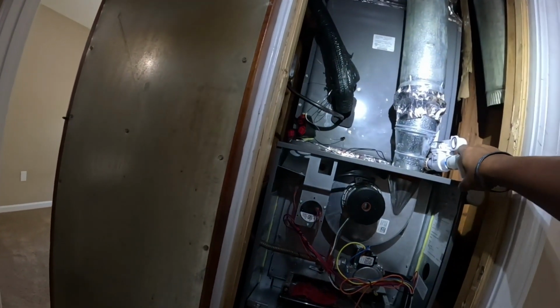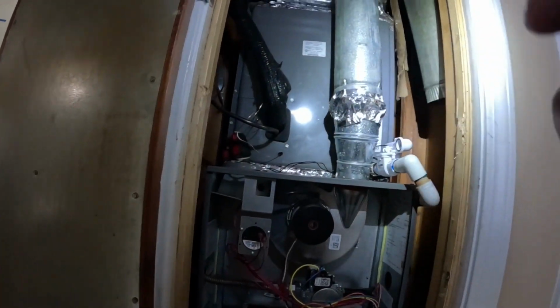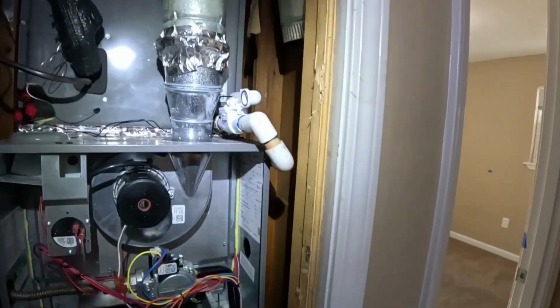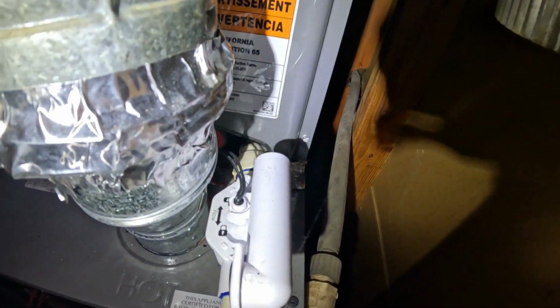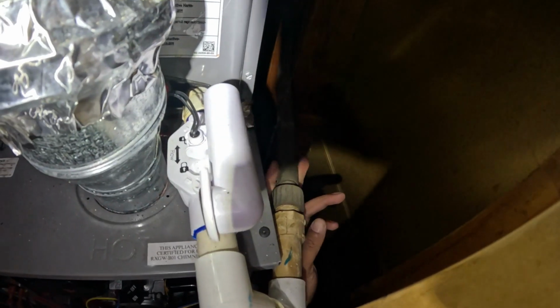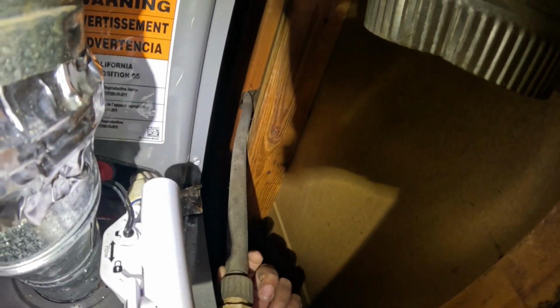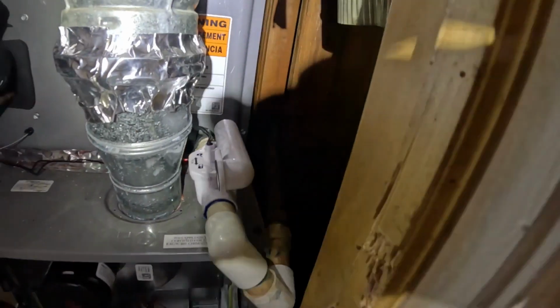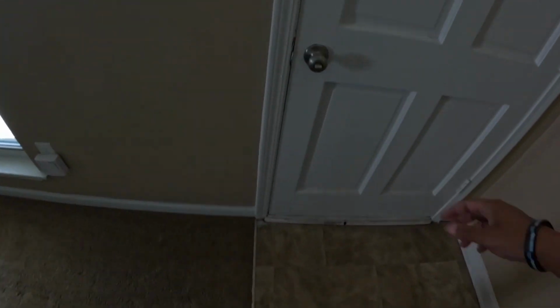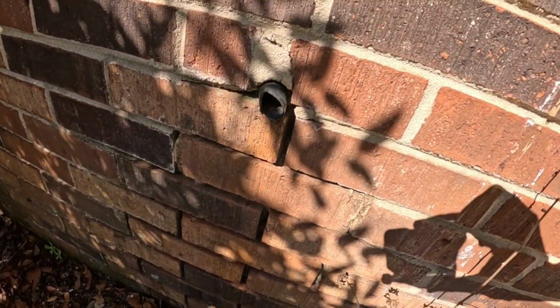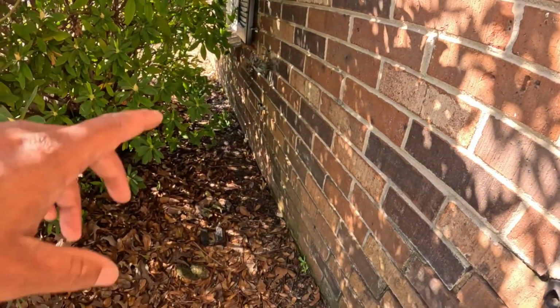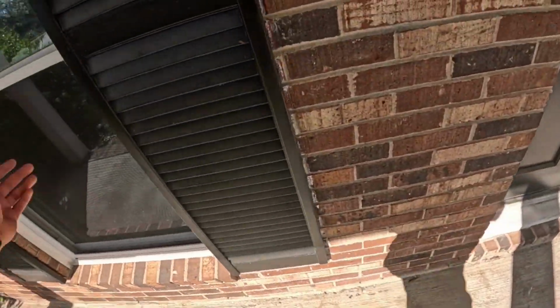I'm also gonna flush this drain line down, I don't know if I said that on camera yet, but they've got, come on magnet, they got the PVC just coming straight out of here, and I can't remember what this tubing is, but it's definitely not PVC, that's all I can say. And it literally just runs straight outside, I'll show you guys that real quick. Comes right outside, it terminates right here. I don't see any other penetration except for the spigot right there, so I'm just automatically assuming that's it. And it kind of lines up with the wall and everything, because there's a bedroom right here on the left side of the closet where the furnace is.